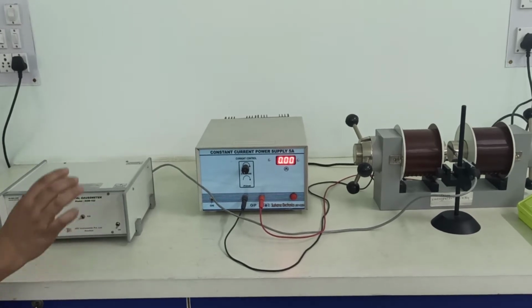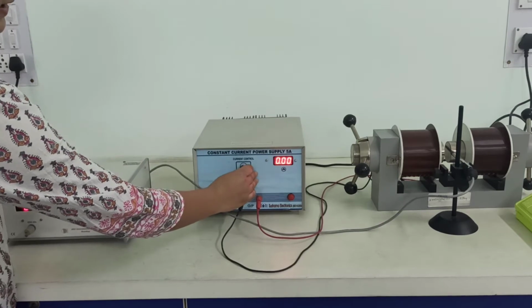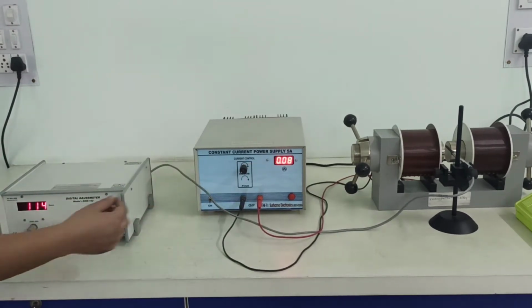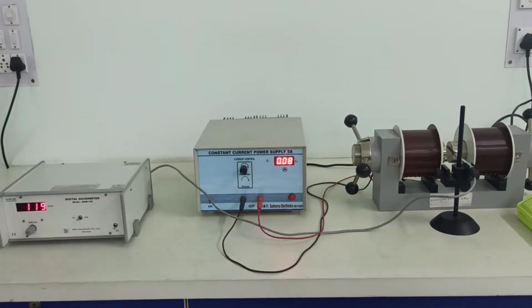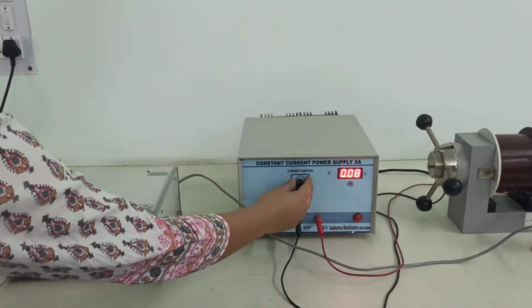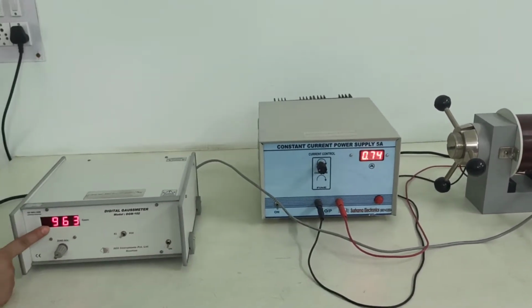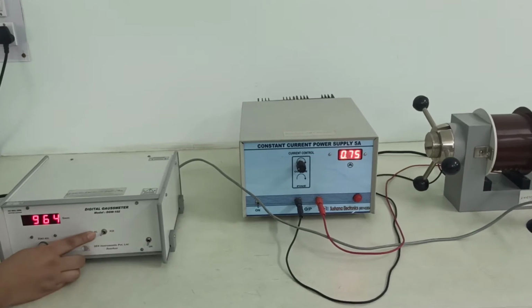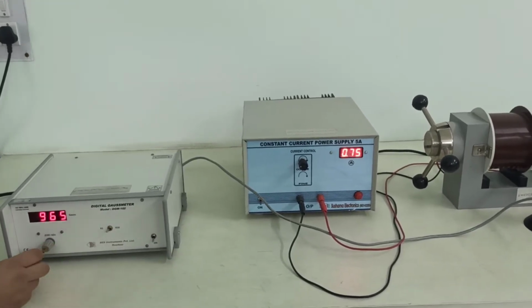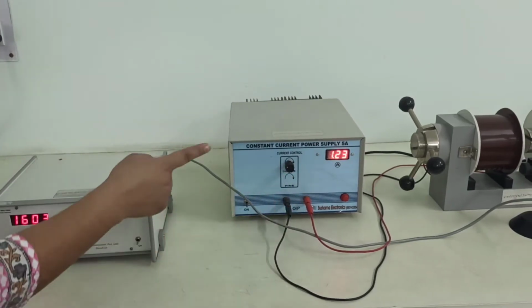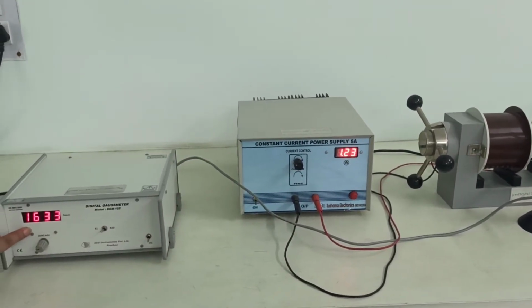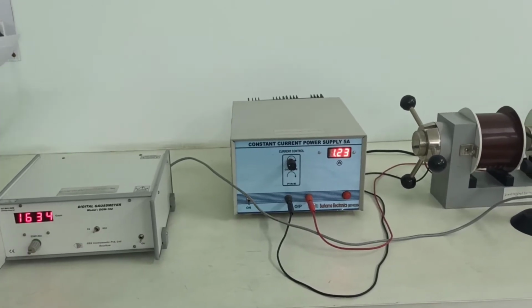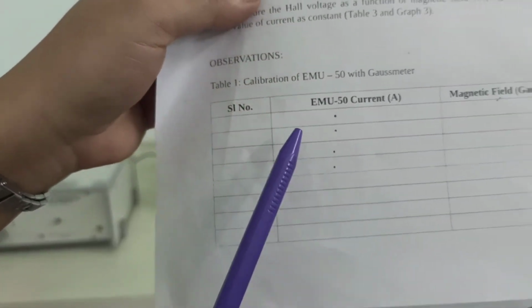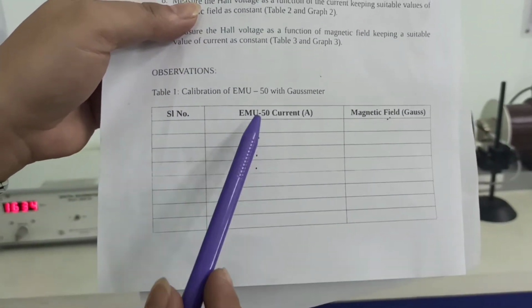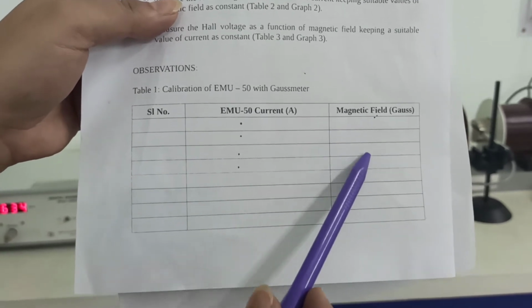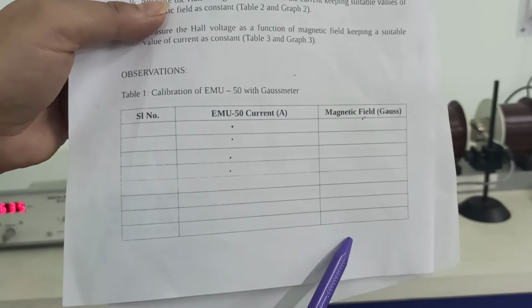Now for calibration, it's very simple. So this is table 1. I just increase the current, and as you see here, when I increase the current, the value of the magnetic field also changes. There are two settings, times 1 and times 10; whatever your requirement, you can choose accordingly. When I keep changing the current, my magnetic field value also changes. So that is your table 1. You fill in your current here, whatever is being supplied from your instrument, and whatever values of magnetic field you get using your Gauss meter, you put down here.